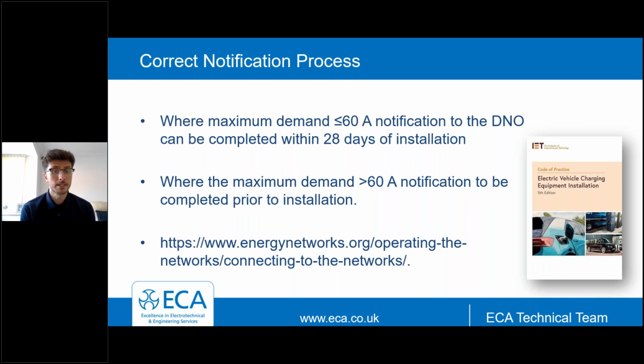However, where the maximum demand is in excess of 60 amps, notification of the addition is going to need to be carried out prior to installation. So the network provider, the DNO, can confirm that it's going to be suitable to add that additional loading to the existing system. Now, there is a website link on the PowerPoint at the minute. If you want to have a look at further guidance and information around that notification process, that can be found on the Energy Networks website.